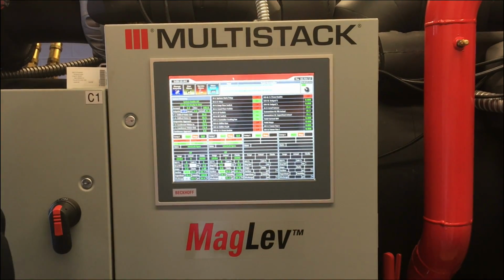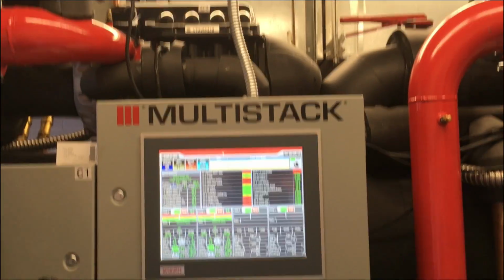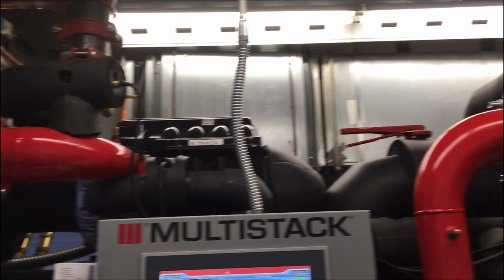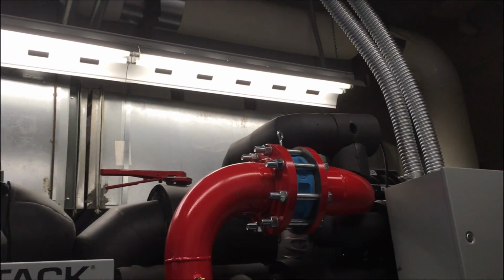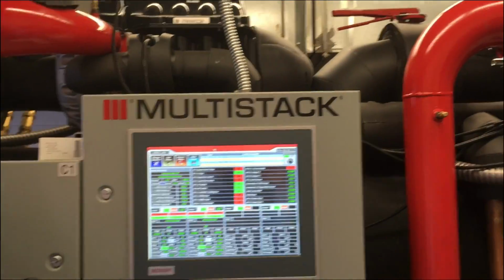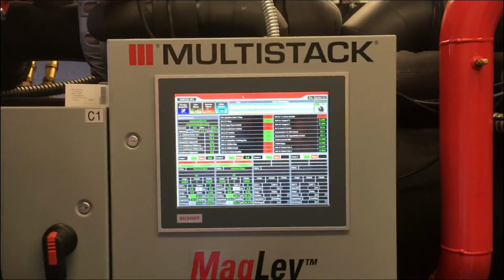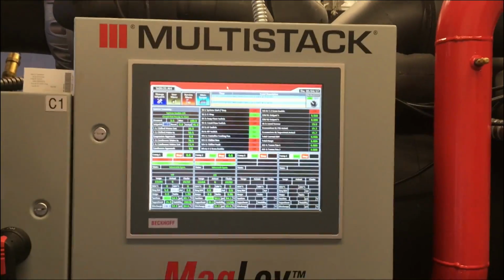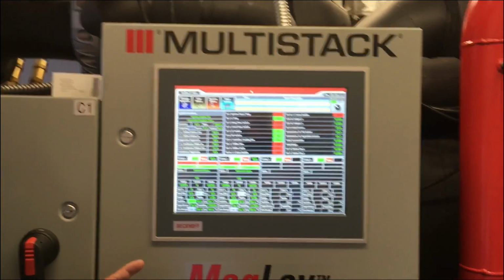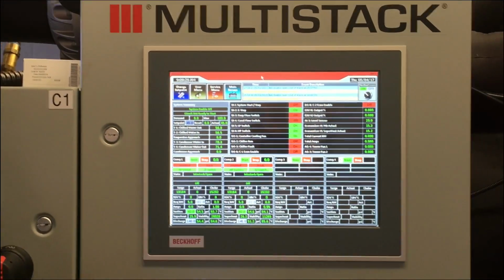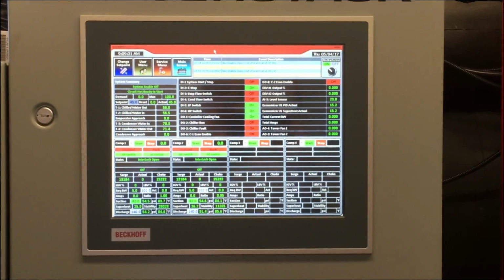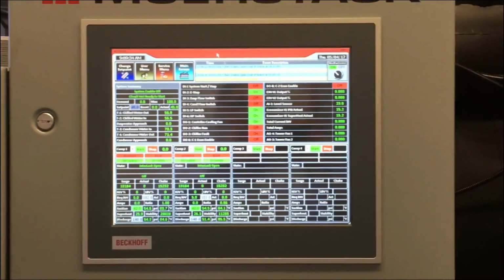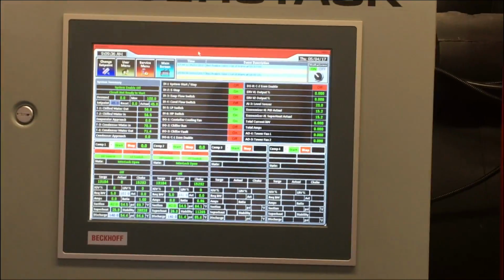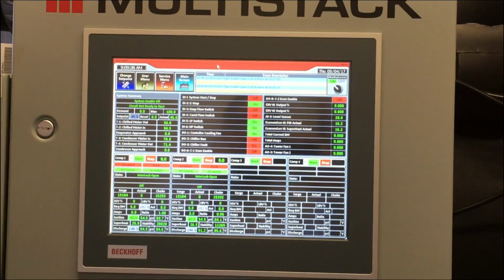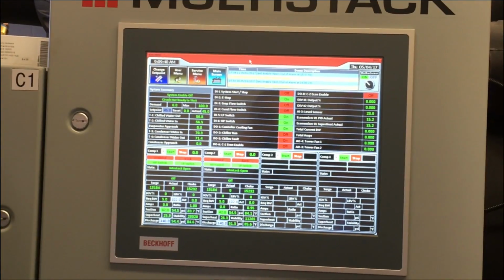So you have two compressors, Turbocor. Each one of those compressors is an oil-free centrifugal, has a motor on a shaft with an impeller attached to the front of that shaft. And basically all we do is pick that shaft up in a magnetic field and float it with no metal on metal contact, and we speed up and slow down the impeller in the front. The only other moving part in that machine is the inlet guide vanes in the front, just like any other true centrifugal. I don't know if you have a centrifugal on site here.